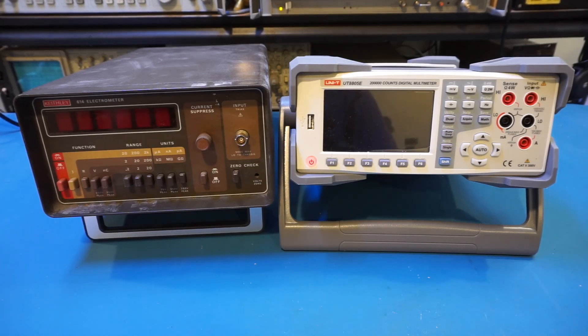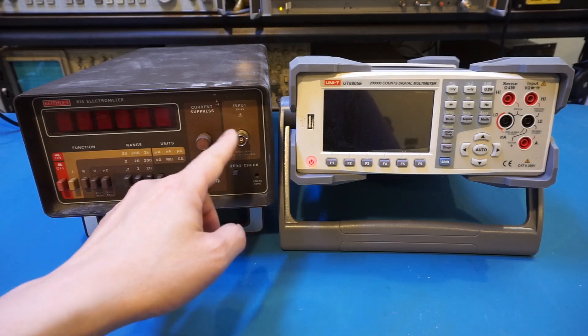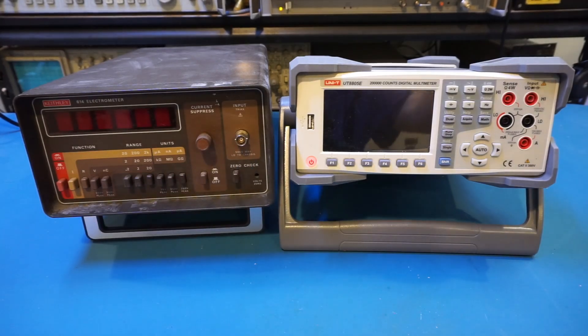Because of the high input impedance, the Keithley 614 uses a triax cable for the input. If you look at the connector here carefully, you will see this is not your traditional BNC. And the cable itself is not cheap. I think just for the triax cable itself, I paid more than $100.